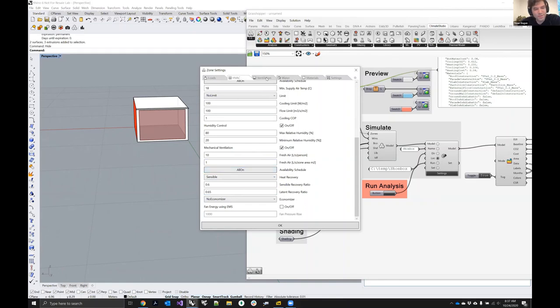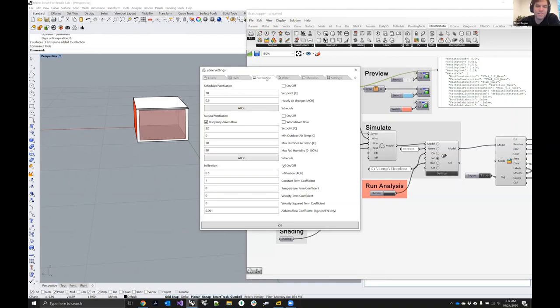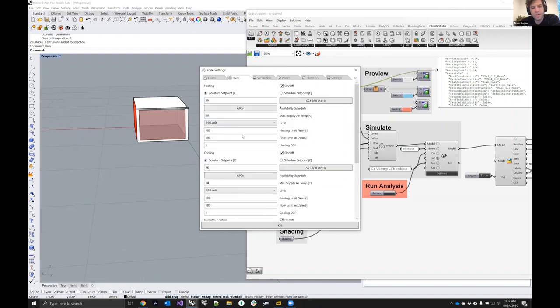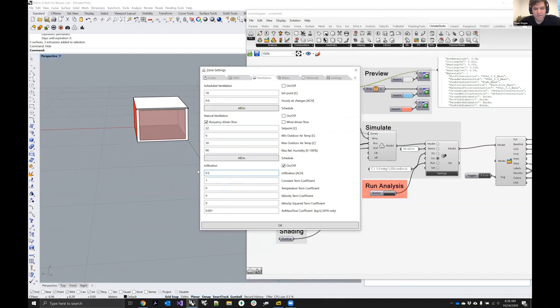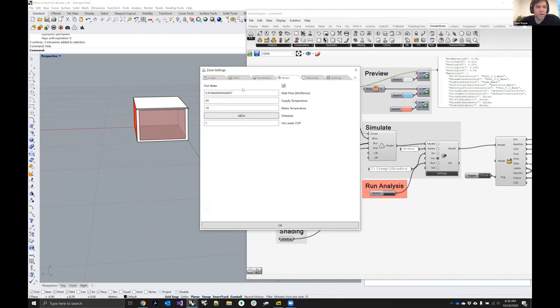The ventilation tab lets you try natural ventilation schemes. You have to coordinate carefully: if you naturally ventilate and cool at the same time, you'll get unreliable results. At the bottom is the infiltration rate, probably the most interesting setting for a fully conditioned building. Currently it's set to 0.5 air changes per hour, which is a fairly airtight modern building. You can also model hot water demand.